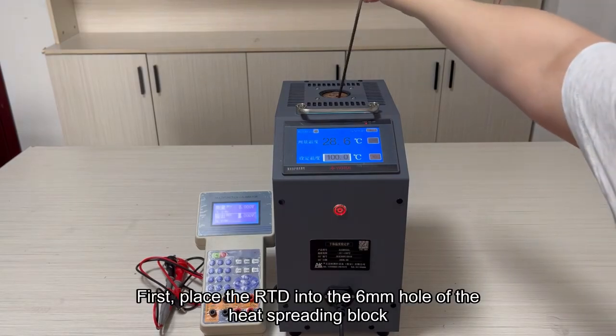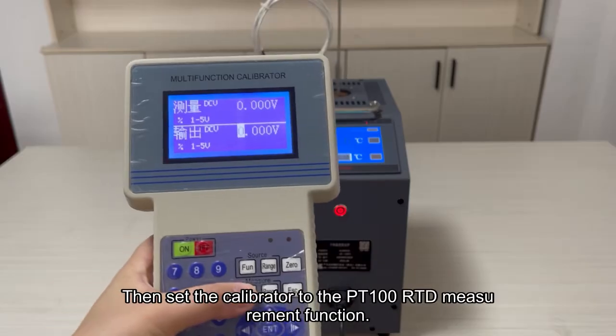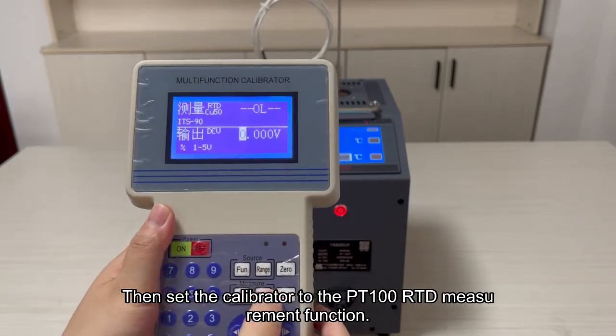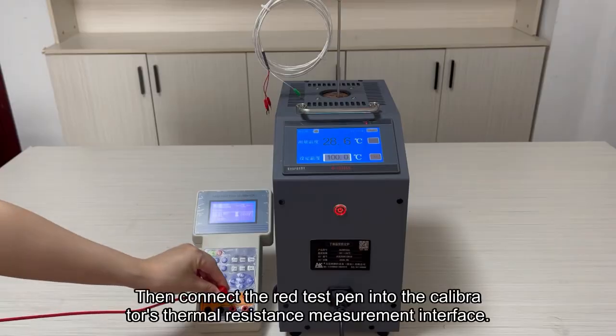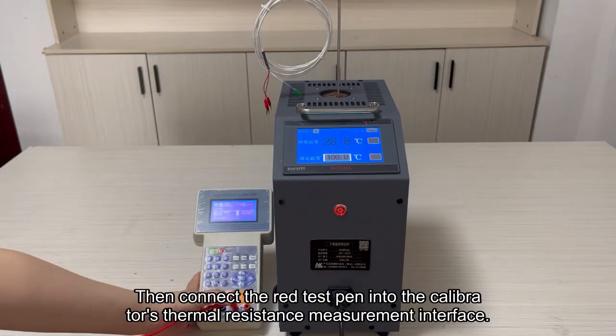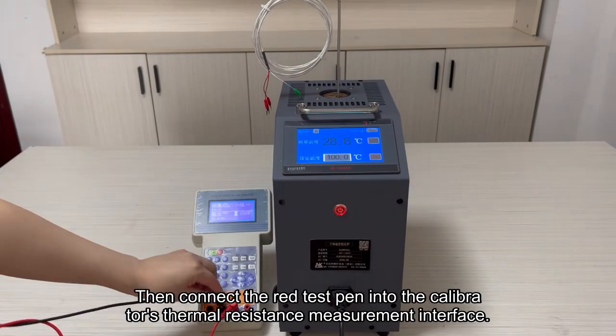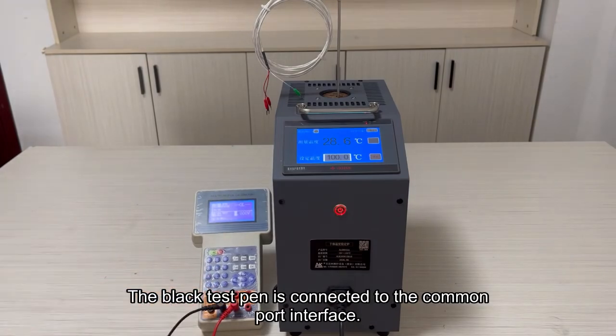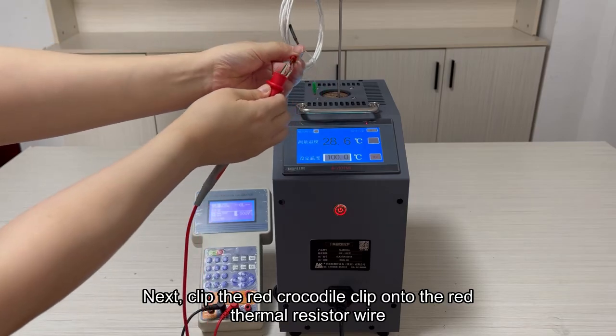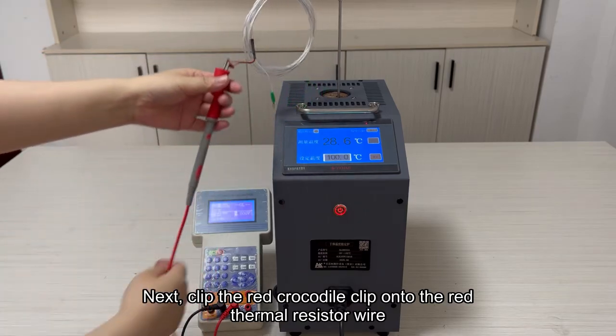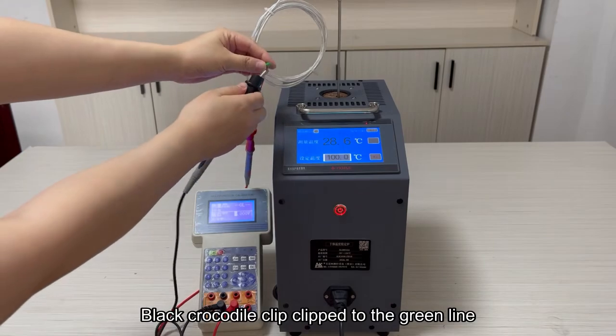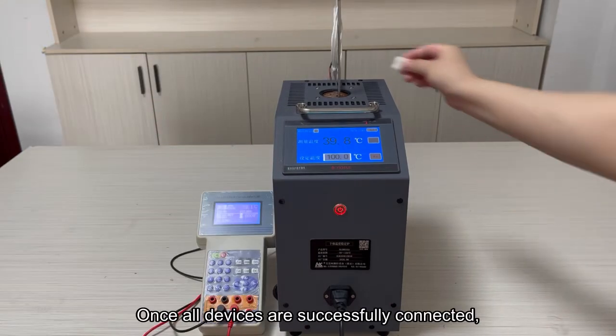First, place the RTD into the 6mm hole of the heat spreading block. Then set the calibrator to the Pt100 RTD measurement function. Then connect the red test pen into the calibrator's thermal resistance measurement interface. The black test pen is connected to the common port interface. Next, clip the red crocodile clip onto the red thermal resistor wire. Black crocodile clip clipped to the green line. Once all devices are successfully connected.